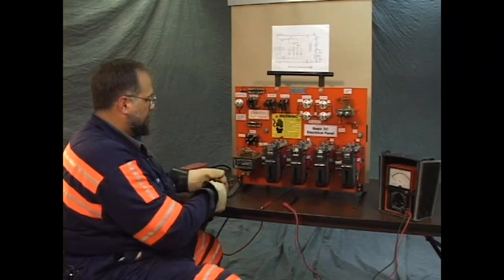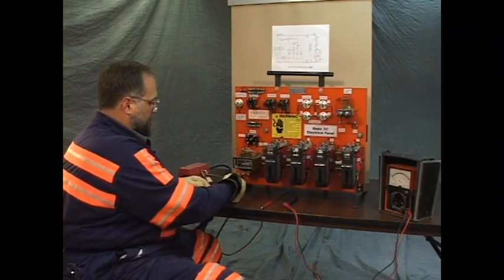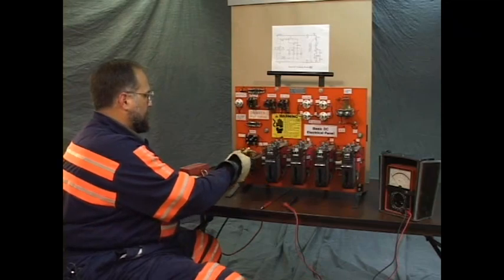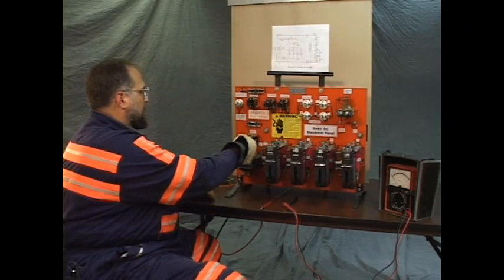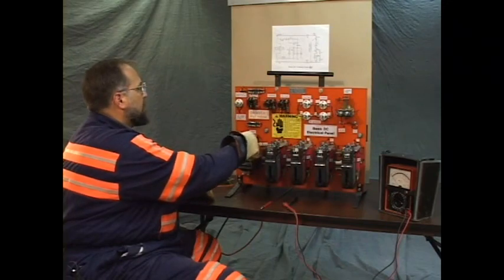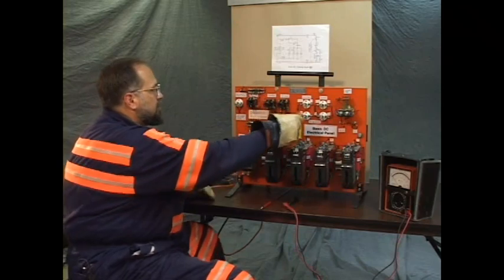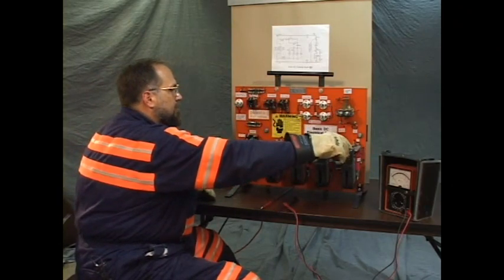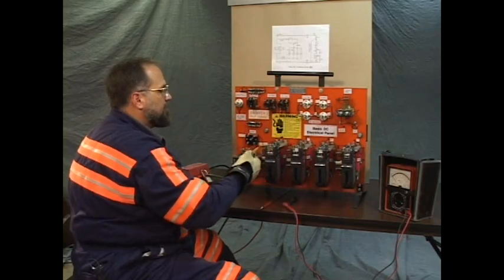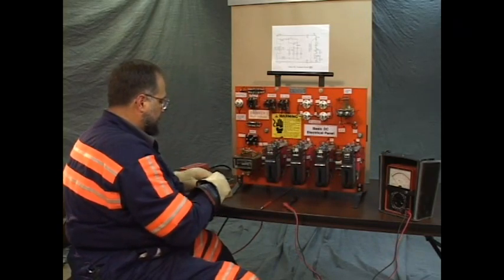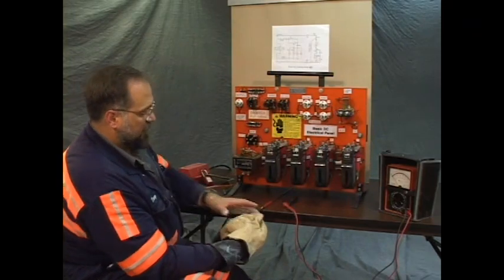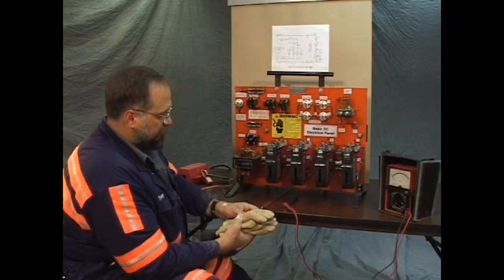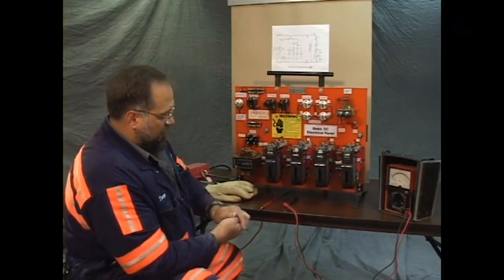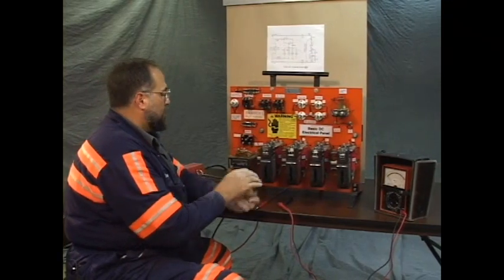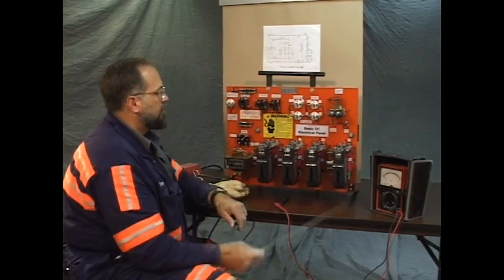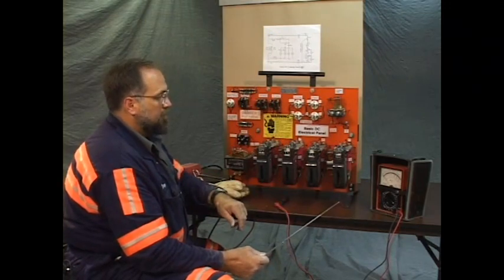I'm using our tick tracer type voltage detector. You'll get the occasional chirp caused by moving too fast. That's not indicative of any power. It's a constant chirp, and it'll flash the light when you have power. It won't show anything. I believe we're safe. Let's take our gloves off. When we operated the panel with the problem on it, we noticed that we had no lights operating, as well as no holding circuit.